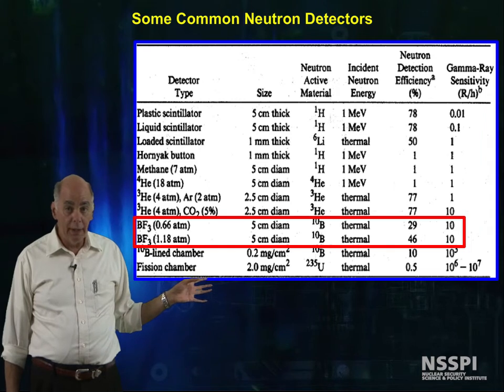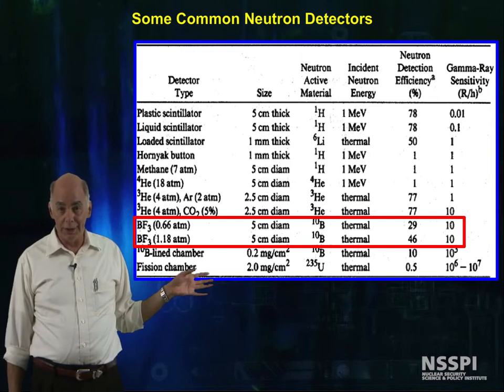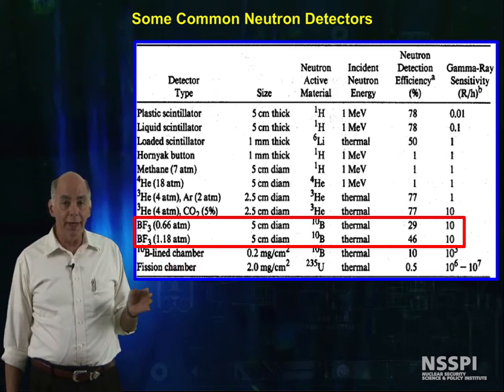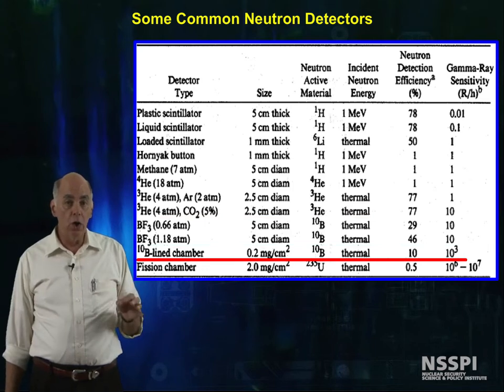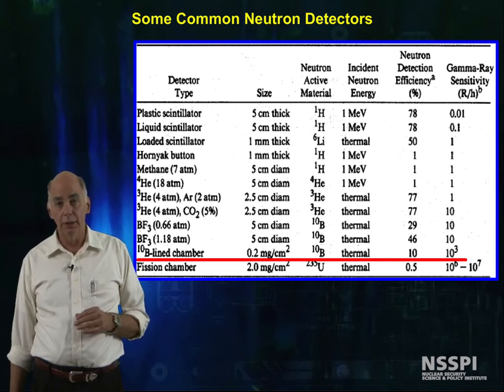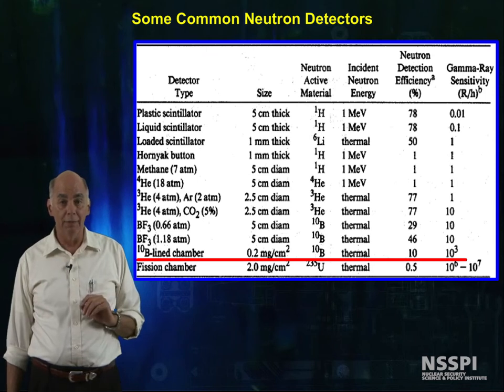With BF-3 chambers, depending on the loading, I can get somewhere between a 29 to 46% detection efficiency for thermal neutrons, and I can discriminate against a 10 R per hour gamma field. With boron-lined chamber, I can have a thermal neutron detection efficiency of about 10%, and I can discriminate against a kilorad of gamma interference.